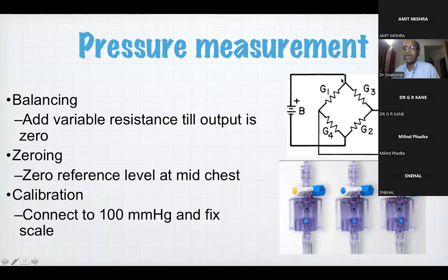So if you have the Wheatstone bridge, this is called the Wheatstone bridge. In a neutral position, the current that is passed through these resistors will come out as a standard output, and the standard output is recorded by the machine as 0. So whenever the diaphragm moves either posteriorly or anteriorly, depending on the pressure that is generated by the fluid filled system, the diaphragm will change these resistances at G1, G2, G3, and G4, and the current output will vary from time to time. This varying current is displayed on the monitor as a pressure trace.